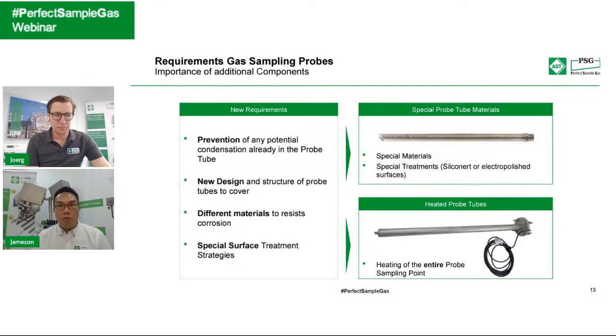I want to share my experience. There's no right or wrong answer. Throughout all these many years, the PTFE tube seems to have some resistance against corrosion. However, because of the sticky dust, the whole tube will eventually clog up, and there's no way to back purge to clear the sticky dust without removing the entire probe. So my answer to the audience is, get yourself prepared, pay a little bit more, and get the 180 degree heated sample tube.